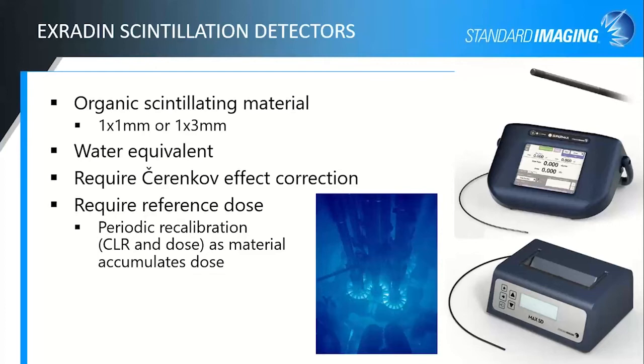And then they're also not absolute dosimeters. So they do require a reference dose. You would cross-calibrate these in a field with a known dose, either your reference 10 by 10 field, or if you're talking smaller fields, you might do a daisy chain more at 4 by 4 or 5 by 5. And they do need a periodic recalibration, both for the CLR, which is Cherenkov light ratio, and for a dose characterization as the material accumulates dose. It is a plastic, just as we've seen plastic phantoms yellow with age. As they're irradiated, the clarity of the plastic does decrease, which affects the spectrum that's transmitted through it. And so that both decreases your signal as well as changes a little bit of the balance between the scintillation and the Cherenkov light.